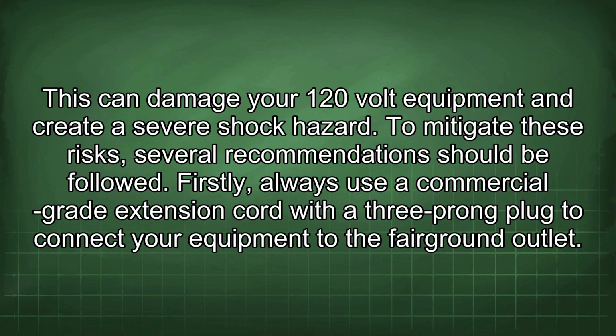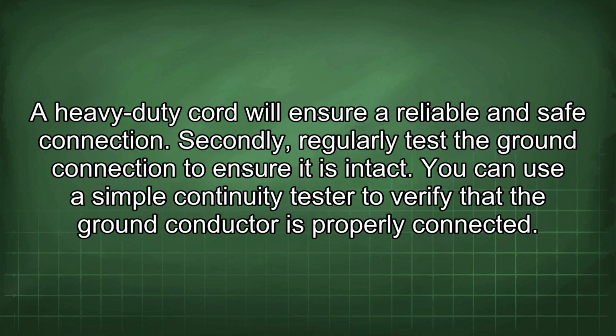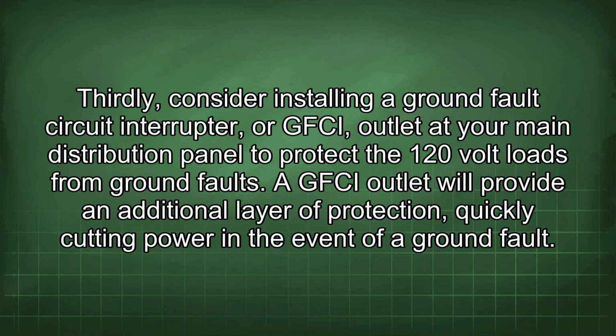Firstly, always use a commercial-grade extension cord with a 3-prong plug to connect your equipment to the Fairground outlet. A heavy-duty cord will ensure a reliable and safe connection. Secondly, regularly test the ground connection to ensure it is intact. You can use a simple continuity tester to verify that the ground conductor is properly connected. Thirdly, consider installing a ground fault circuit interrupter, or GFCI, outlet at your main distribution panel to protect the 120-volt loads from ground faults.